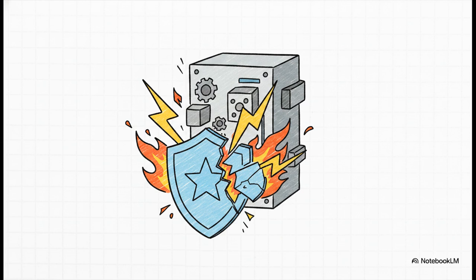The fuse is basically acting as the ultimate sacrificial bodyguard. Its entire job is to clear a short circuit fast and cleanly, well within the contactor's own thermal and mechanical limits. By keeping that fuse rating lower, the system ensures the fuse blows completely before the contactor itself takes permanent, catastrophic damage from the extreme heat and stress of a fault.